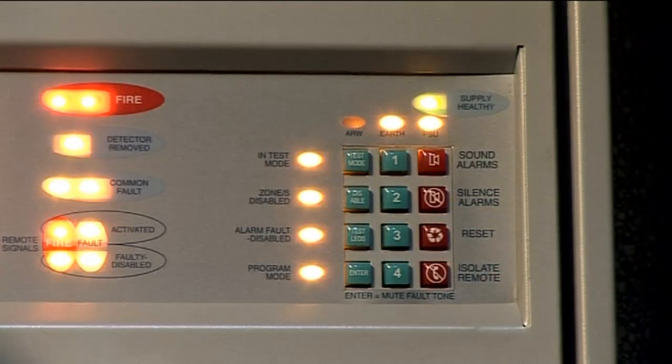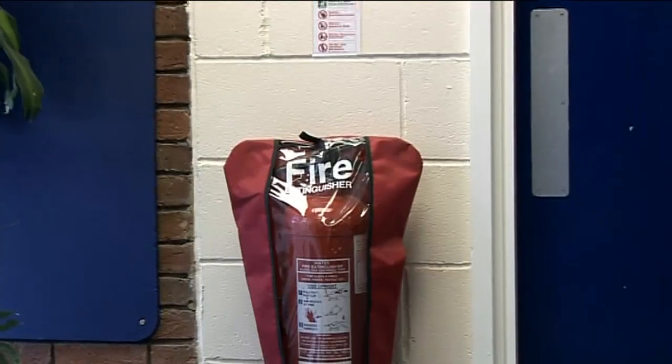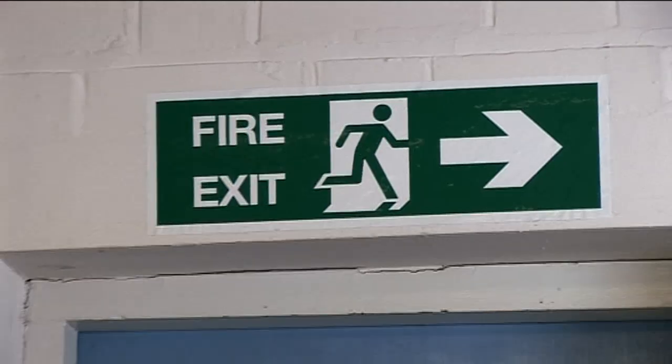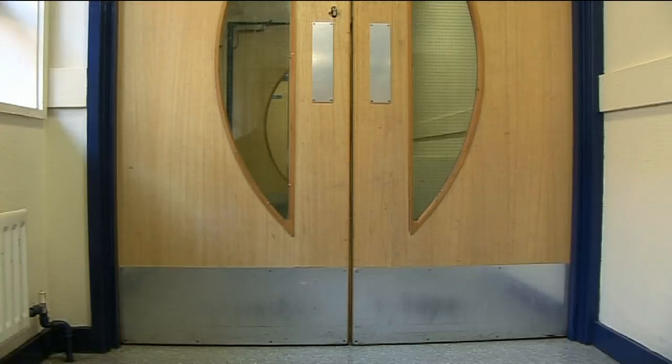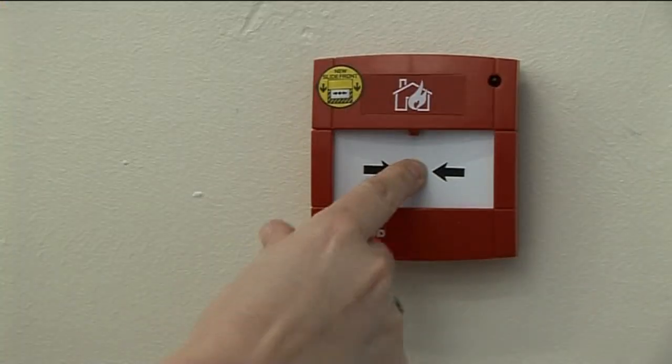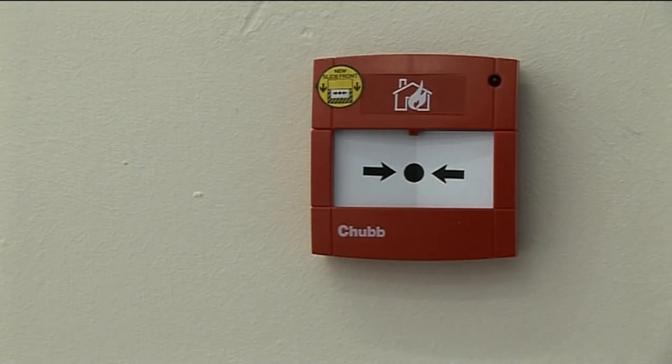Existing fire safety precautions should also be assessed to check whether they are adequate or in need of improvement. This should include considering fire alarm and detection systems, firefighting equipment, emergency lighting and signage, as well as fire doors, fire stopping, and the construction of the building. All schools should have a fire alarm with call points. Some schools may require automatic fire detection that provides an early warning to allow the maximum time for escape.